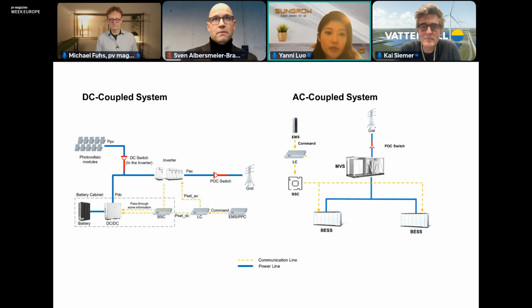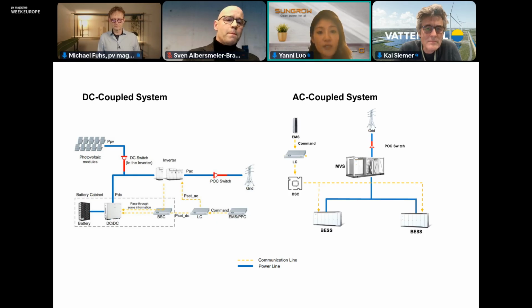With DC coupled solutions, it's a bit more complicated, as you can see on the left side of the diagram. We divide it into day mode and night mode. Simply put, if the network circuit breaker is off, it's disconnected, that's night mode, and the BESS can discharge into the grid. Unfortunately, because of grid connection applications and VDE certification requirements, currently we can only discharge the BESS or the PV into the grid, but not charge the batteries with energy from the grid.